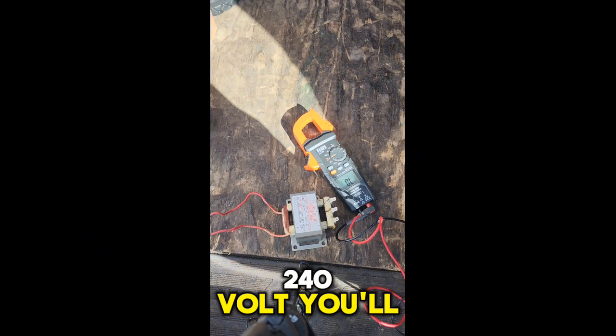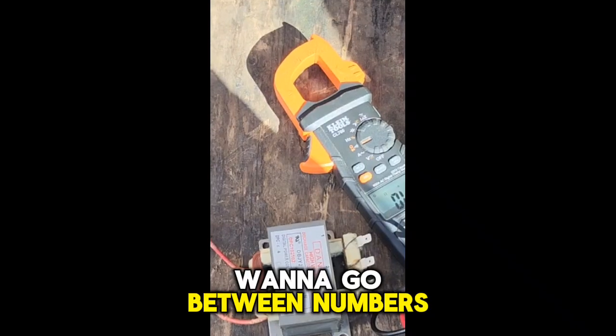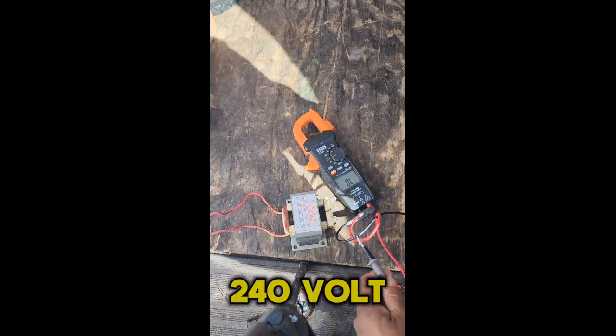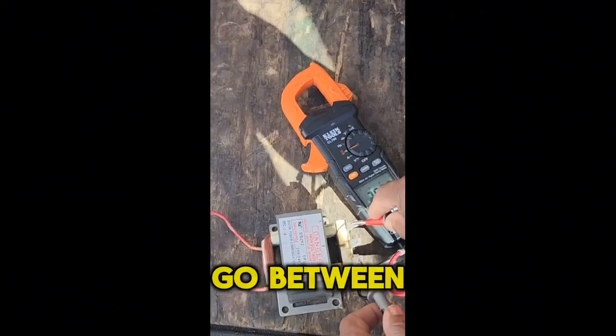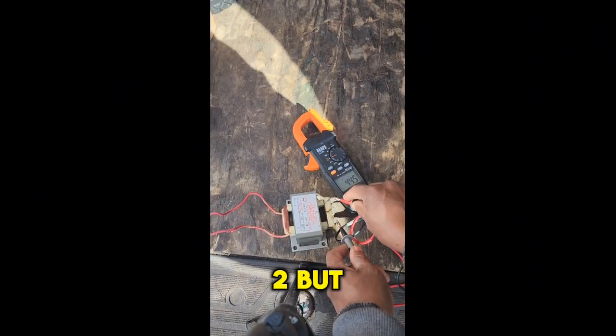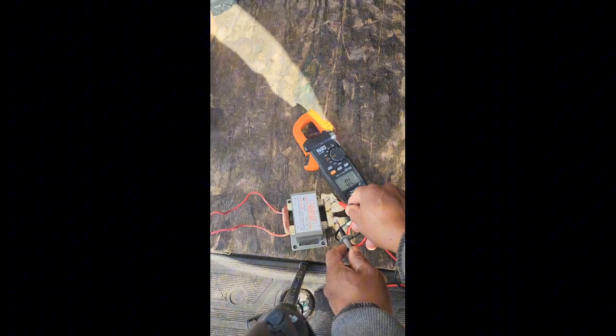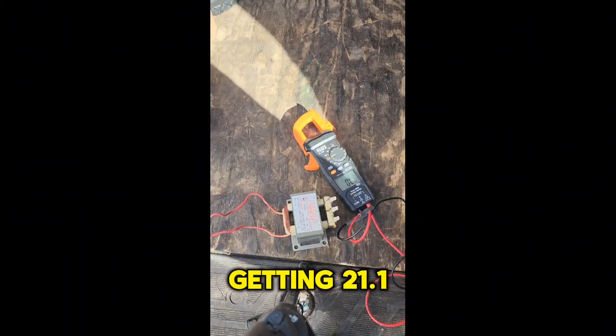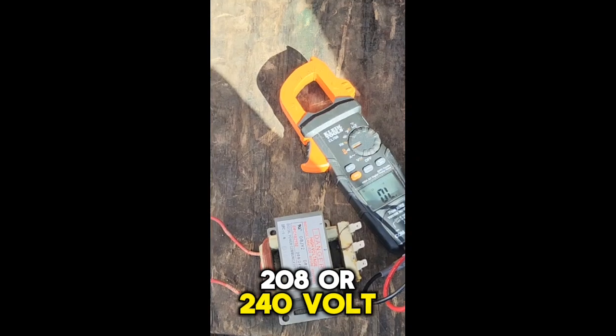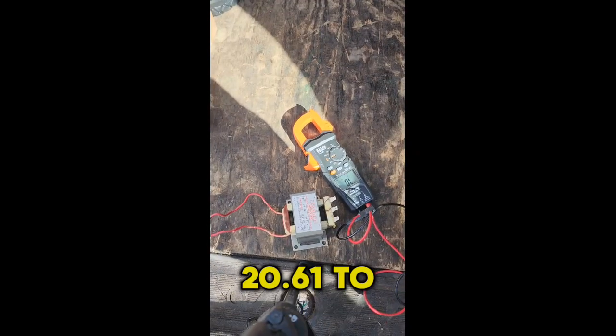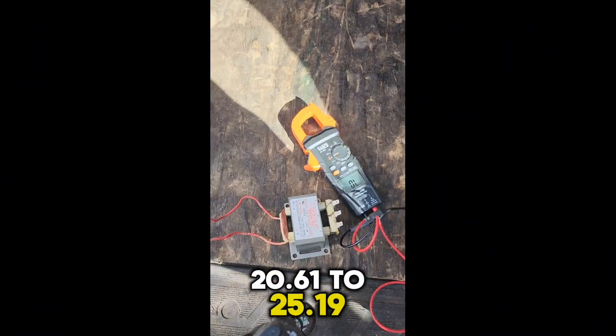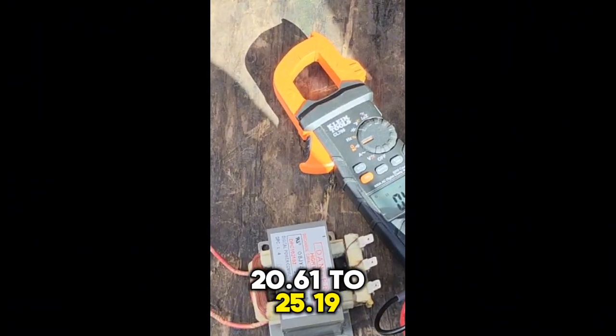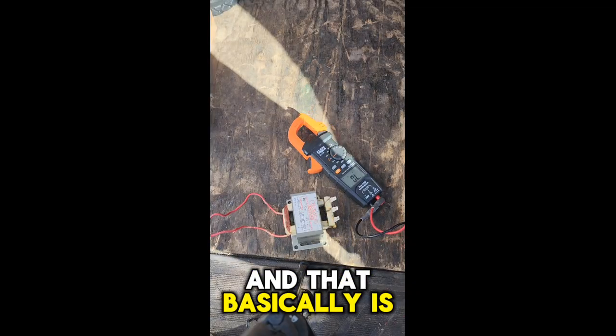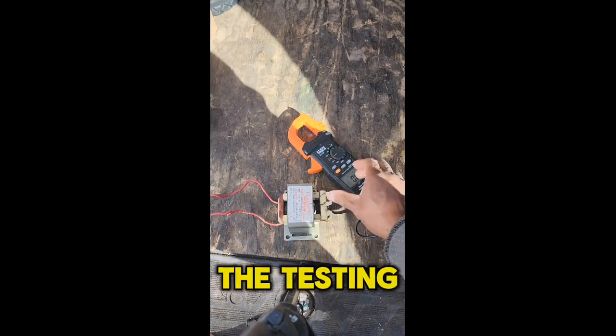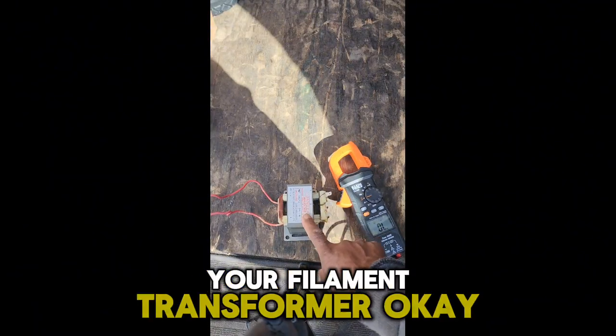If you have a 240 volt, you'll want to go between terminal 1 and terminal 3. If you have 208, you're going to go between 1 and 2. But see, I'm going between 1 and 3, and it looks like we're getting 21.1. And for 208 or 240 volt, you want to be between 20.61 to 25.19. And that basically is the testing procedure for your filament transformer.